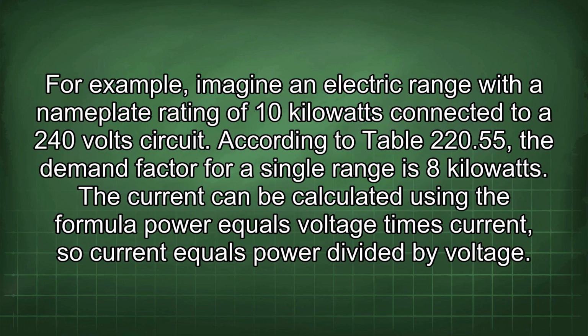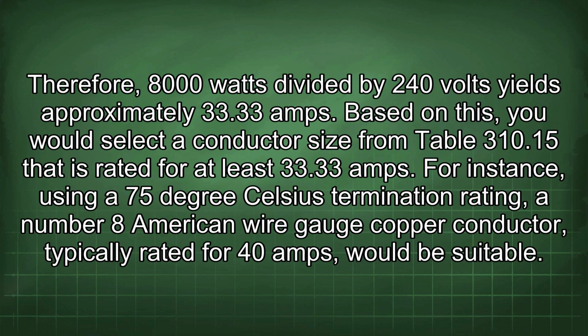210.4b. For example, imagine an electric range with a nameplate rating of 10 kilowatts connected to a 240 volt circuit. According to Table 220.55, the demand factor for a single range is 8 kilowatts. The current can be calculated using the formula power equals voltage times current, so current equals power divided by voltage. Therefore, 8,000 watts divided by 240 volts yields approximately 33.33 amps.